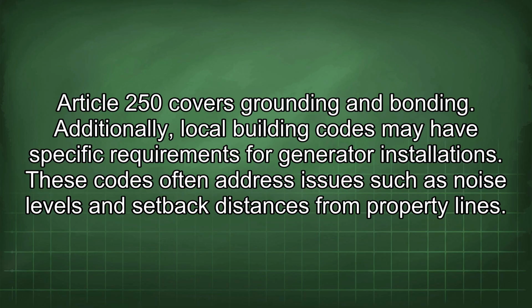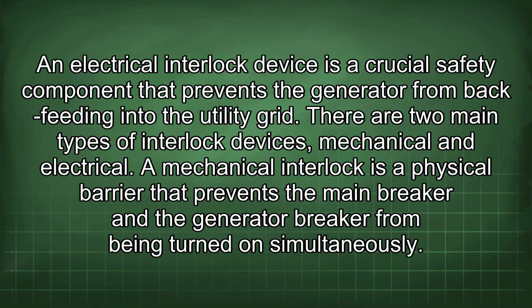Additionally, local building codes may have specific requirements for generator installations. These codes often address issues such as noise levels and setback distances from property lines. An electrical interlock device is a crucial safety component that prevents the generator from backfeeding into the utility grid. There are two main types of interlock devices, mechanical and electrical.